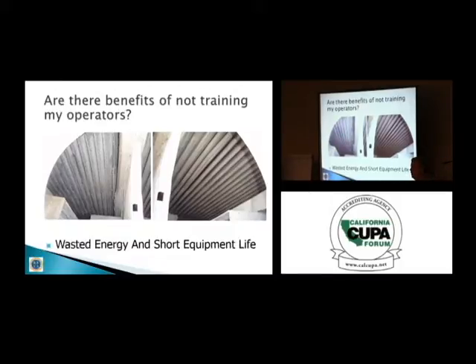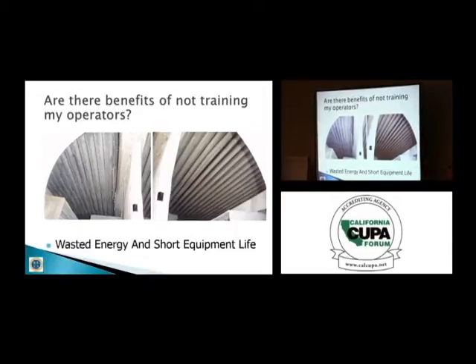This one is scaled up. It saw the water, but we didn't control the quality of that water with respect to its dissolved solids. And so as the water evaporates from the surface, it's leaving the minerals behind. And part of the art of operating a condenser is maintaining a good chemical water dissolved solid balance in the water. So this one wasn't addressed the way it should. So this condenser wasn't giving us the performance we needed: good heat rejection at the lowest price. This user was paying a lot of money for not training his operator to know what to look for and to do.